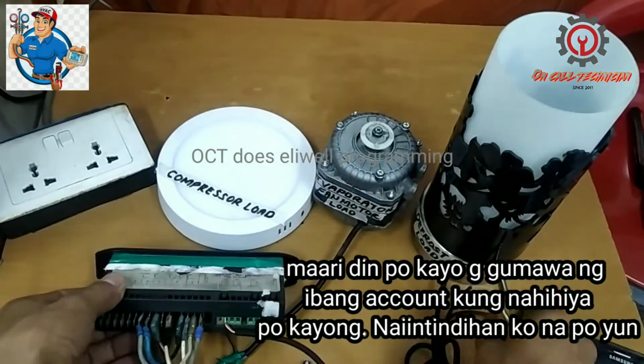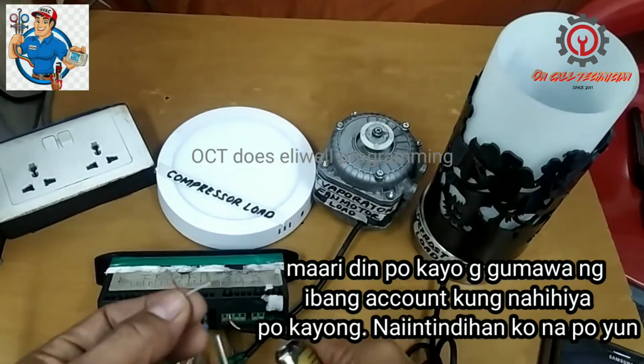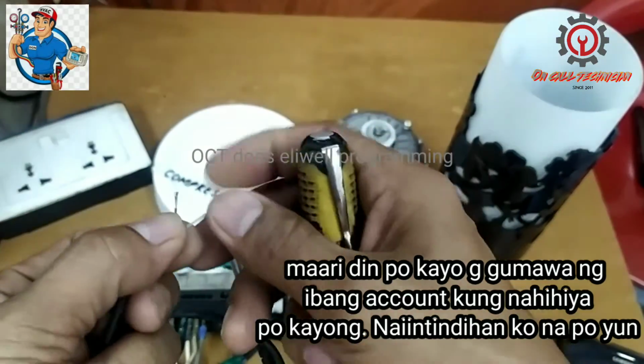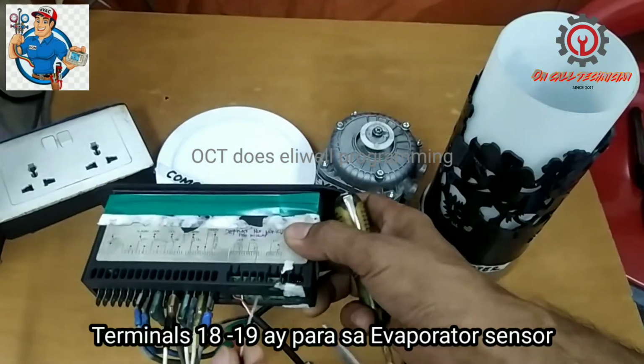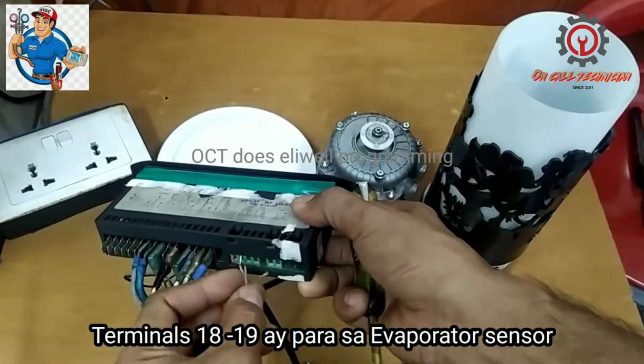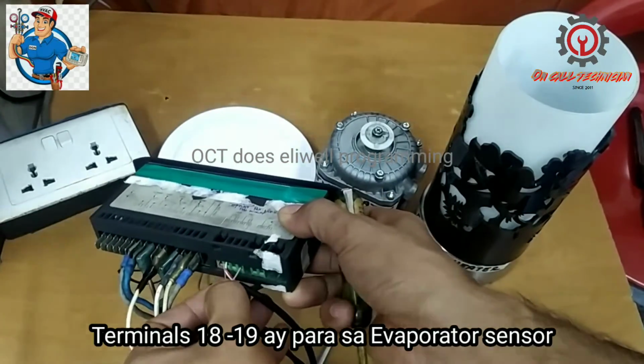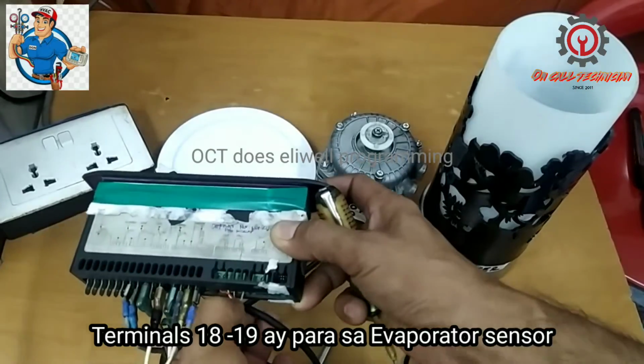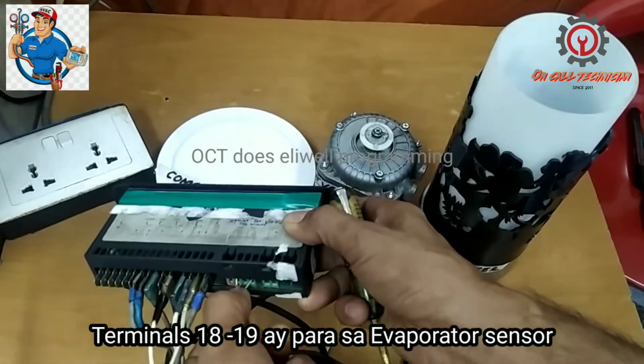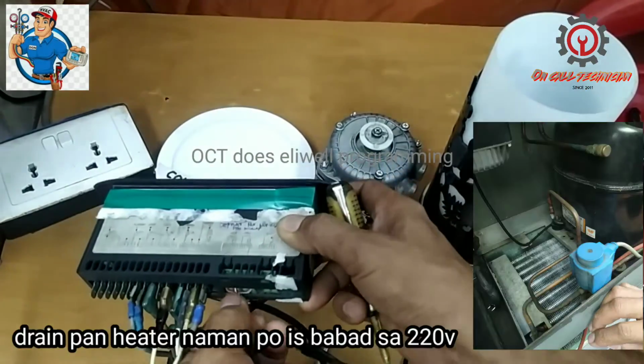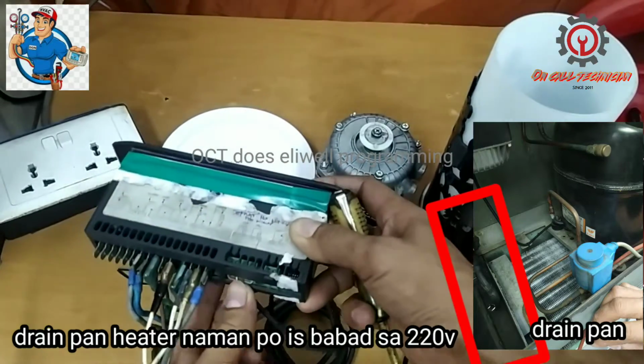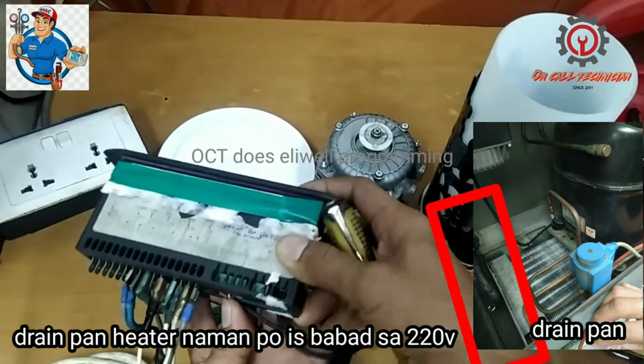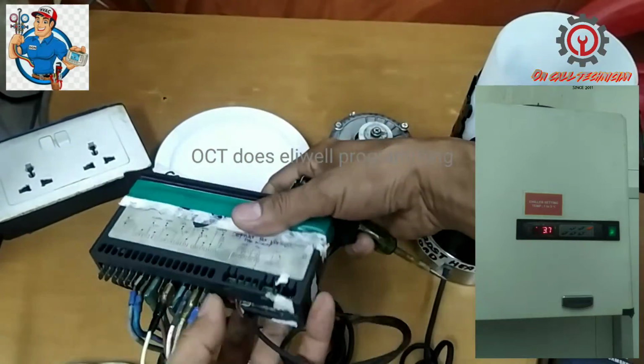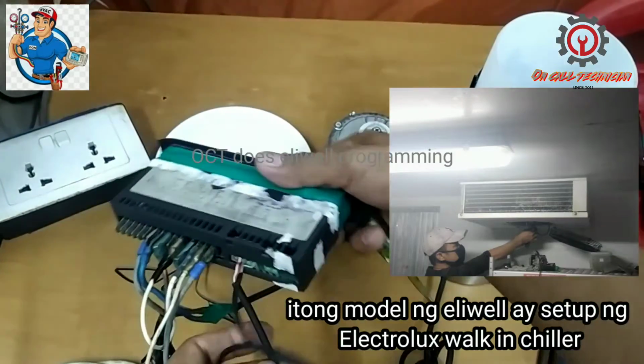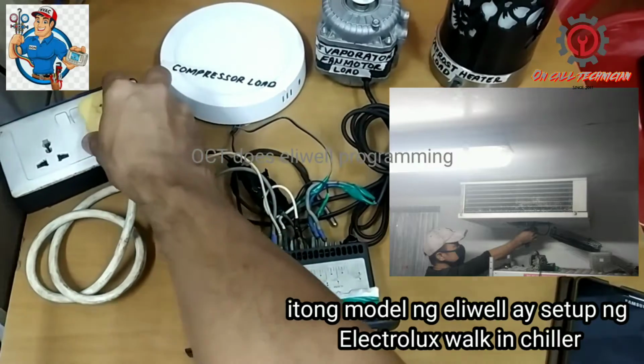Okay, and this another sensor is for the evaporator sensor, which is the PB2. So between the terminal 18 and 19, that is the slot for the evaporator. Okay, that's it. Now let's power it on.